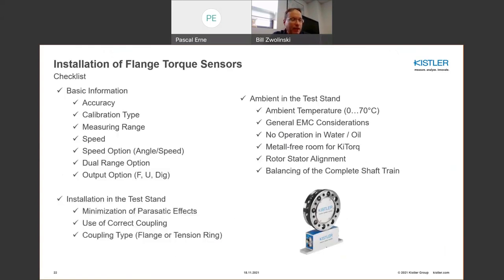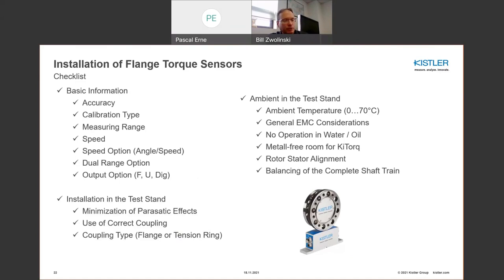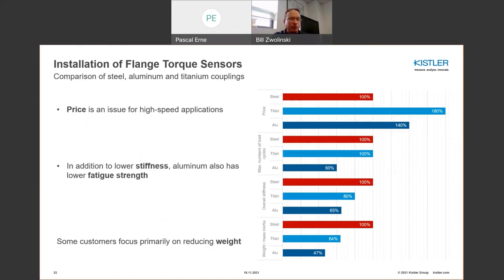For flange torque meters, the same basic selection approach applies: accuracy class, speeds, and whether you need a dual range option for higher startup torque versus running torque. The same rules apply in terms of test stand installation — using the correct couplings, addressing stiffness and frequency performance. For flange torque sensors, you can look at price, materials — steel, titanium, or aluminum. Titanium is famous for high stiffness and low mass but comes at a higher price. Aluminum has the lowest weight density of the three, which can also be a factor in price.